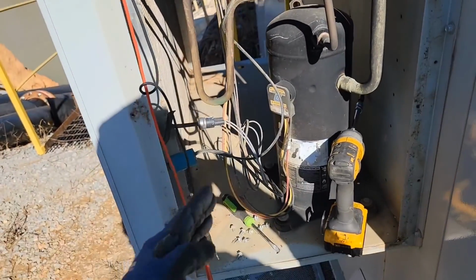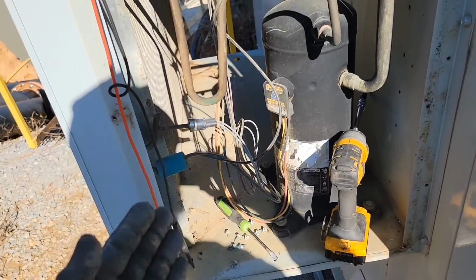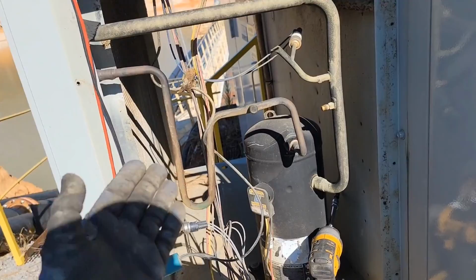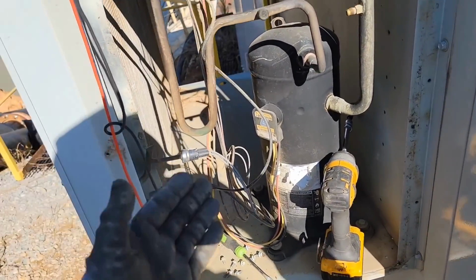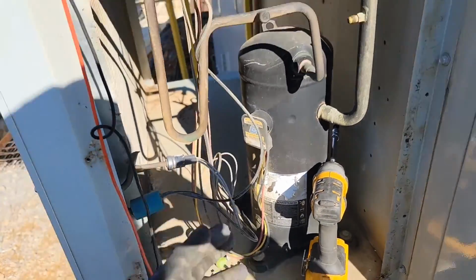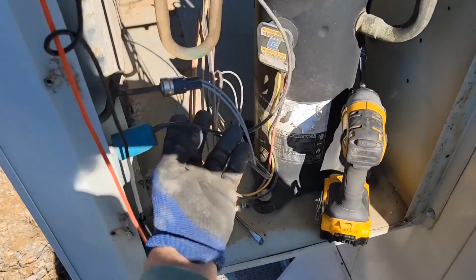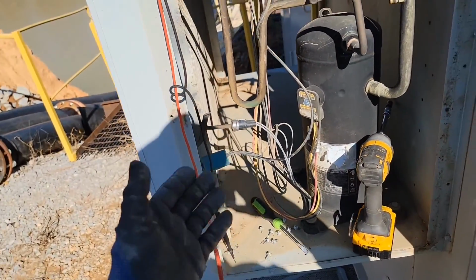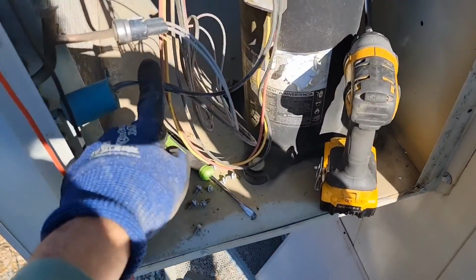As long as you monitor pressures, make sure they're not high, then you can go ahead and have this unit working, and that will buy you some time and give the customer some cooling until you can get a new pressure switch, okay? But you gotta make sure there's not a high pressure situation, right?